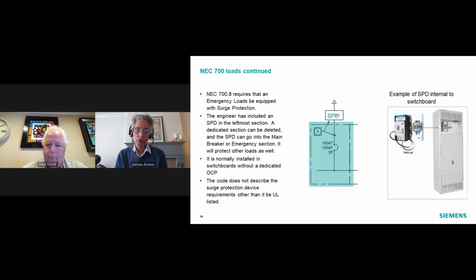The code doesn't describe the surge protection device. It basically just says that it should be UL listed. And what you want there is, at the minimum, a UL 1449 4th edition SPD. And then as an engineer, it's good to specify ratings and features based on the particular location and application you're in. So, probably something more stringent in Florida than in California.